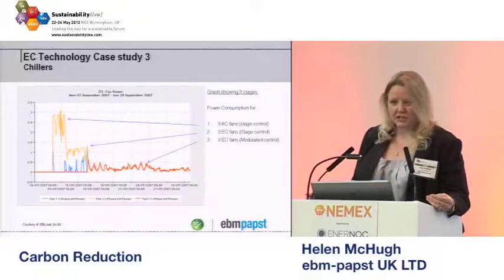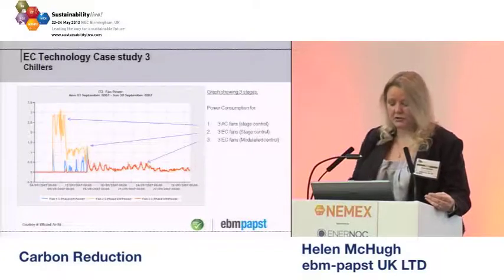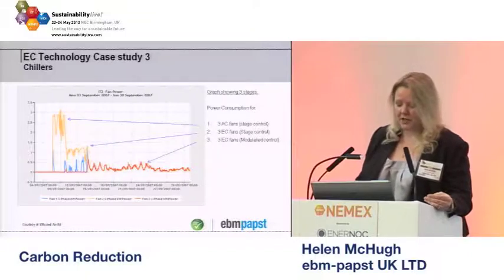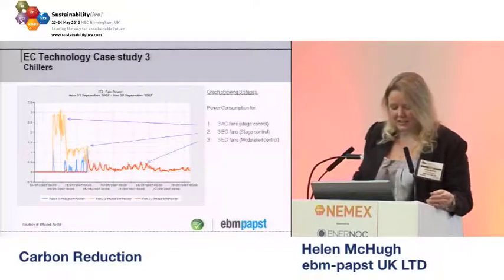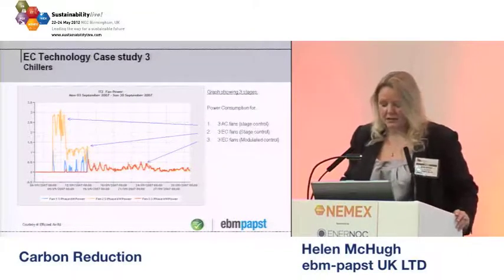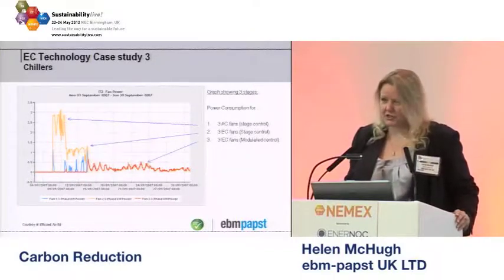But then we looked at modulating the fans. And because of the fan laws, by reducing the speed of the motor, you're massively improving the efficiency, reducing the power consumption. You see there that all those fans are running at the same time now on that other graph. You can't quite see the colours, but they are there. And they're over 70% efficiency saving.